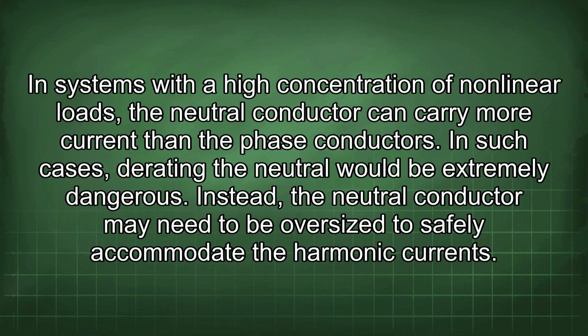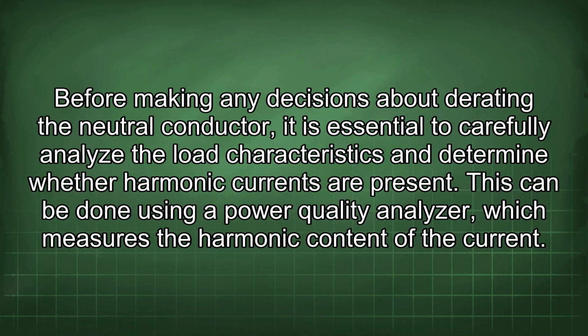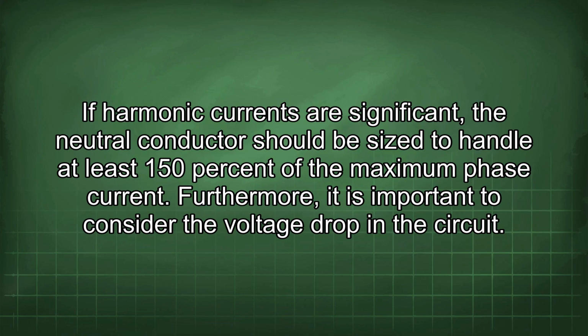In such cases, derating the neutral would be extremely dangerous. Instead, the neutral conductor may need to be oversized to safely accommodate the harmonic currents. Before making any decisions about derating the neutral conductor, it is essential to carefully analyze the load characteristics and determine whether harmonic currents are present. This can be done using a power quality analyzer, which measures the harmonic content of the current. If harmonic currents are significant, the neutral conductor should be sized to handle at least 150% of the maximum phase current.